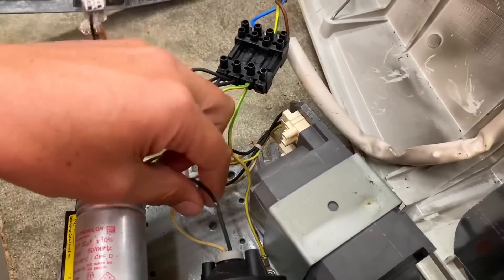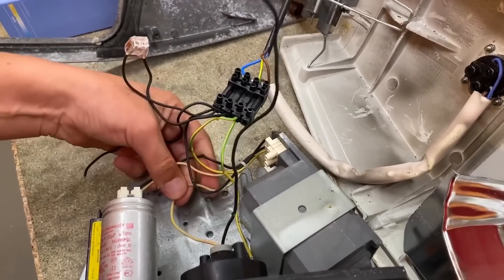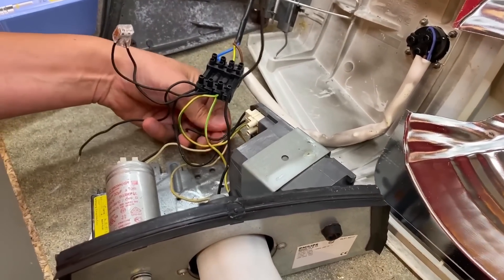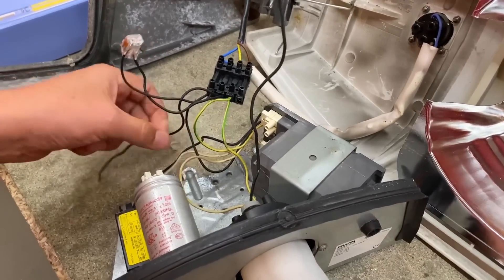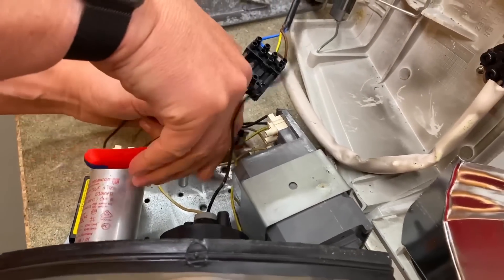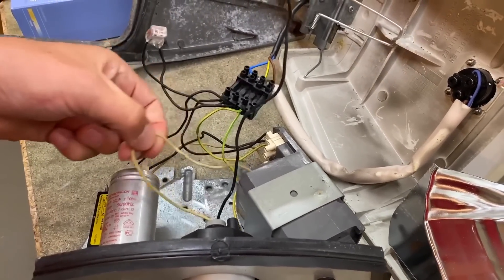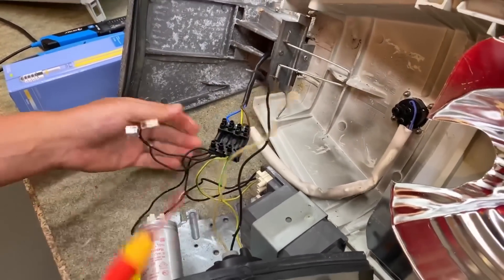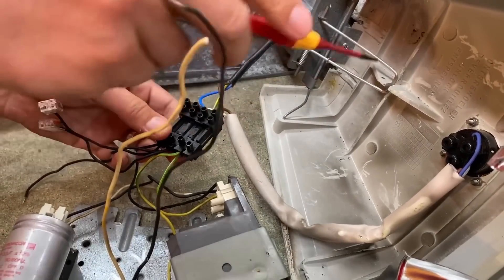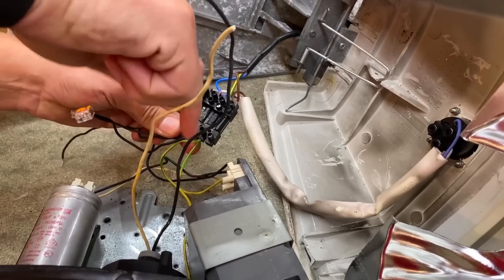So you're popping out the conductors — there's one, and then the other one routes across through to the... Because it's black, everybody's thinking that used to be neutral — and we've got another one that might have been white in the past. I'm just going to snip that because I can't easily get into that screw. So we've got these two now to work out — I'm going to strip out these two terminals. Now you can see the line comes in and then immediately goes up to our photocell and the NEMA socket on the top there — a bit of terminology for you.